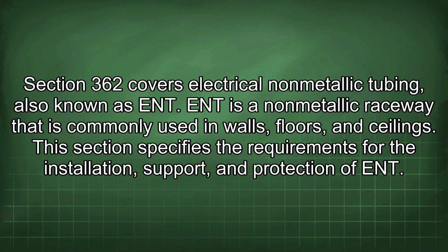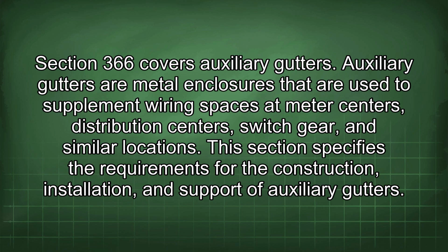Section 362 covers electrical non-metallic tubing, also known as ENT. ENT is a non-metallic raceway that is commonly used in walls, floors, and ceilings. This section specifies the requirements for the installation, support, and protection of ENT. Section 366 covers auxiliary gutters. Auxiliary gutters are metal enclosures that are used to supplement wiring spaces at meter centers, distribution centers, switchgear, and similar locations. This section specifies the requirements for the construction, installation, and support of auxiliary gutters.